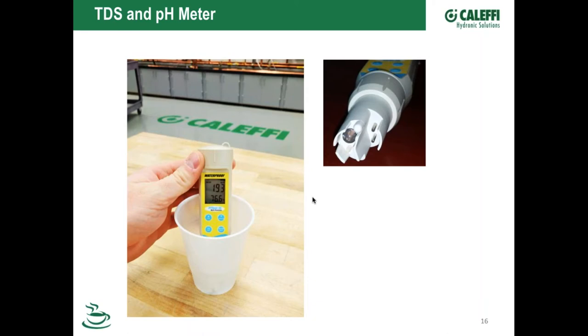You just get a sample of water in a glass or plastic container and stick it in there. On the business end of a TDS meter, you'll see a little porous glass bulb, and that's where it reads the pH of the fluid. These two stainless steel prongs go in there too, and basically what you're looking at is an ohm meter. It's reading the resistance, or the conductivity—the opposite of resistance—of the water across these two prongs as you stick it in.